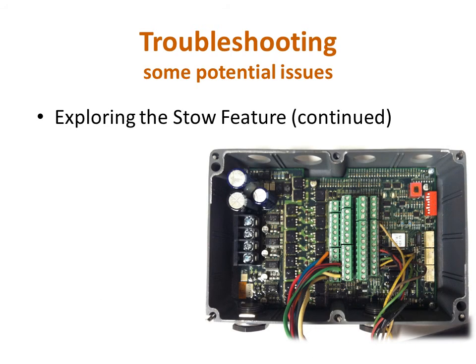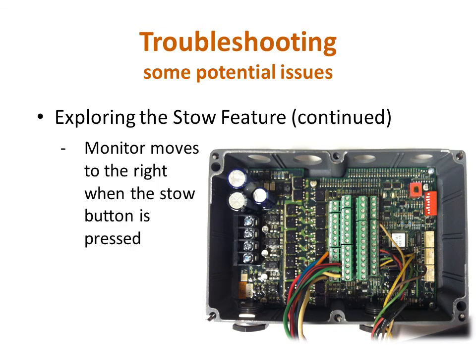For this last example, what if you press the switch to stow the monitor and it rotates instead of stowing? There are 2 likely causes based on the exact behavior of the monitor. If it only rotates to the right as long as the stow switch is held, check to see if you have a 6-wire Stow controller, missing wires on pins 7, 8, and 9, and then make sure that dip switch 1 is in the up position.